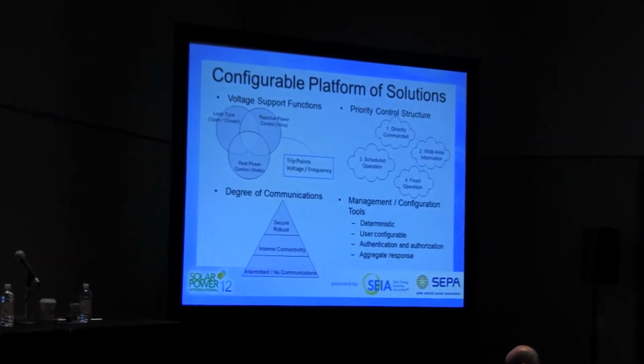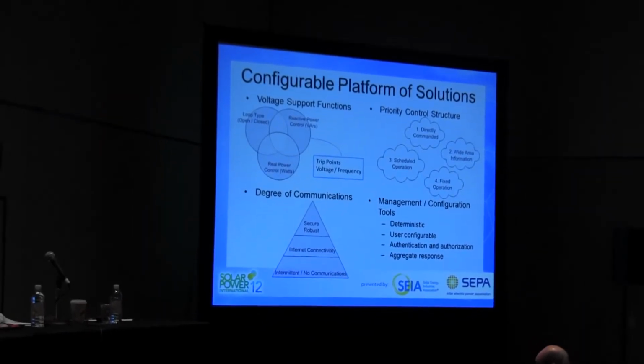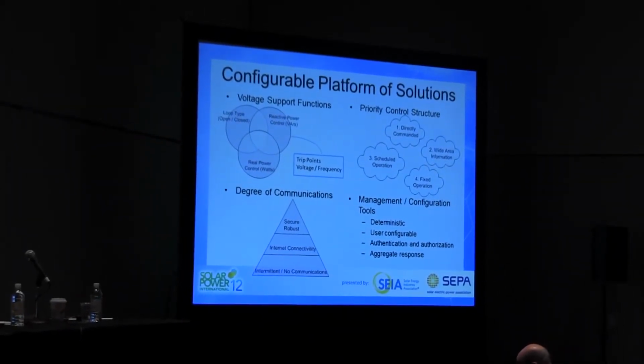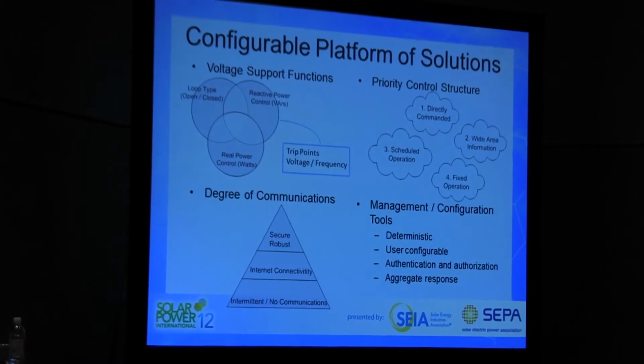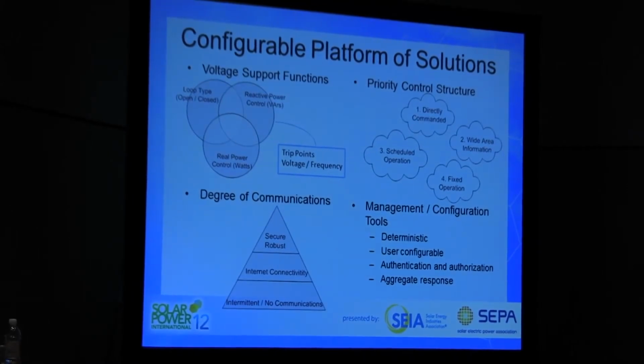We have a number of different configuration environments, with people controlling voltage on each individual circuit differently. So we come up with a configurable platform solution. We have voltage support functions, both open and closed loop, and we're really only able to control real and reactive power—inverters can't do much more than that, real or reactive power or both. We also have voltage and trip points, both in terms of frequency and individual voltage.